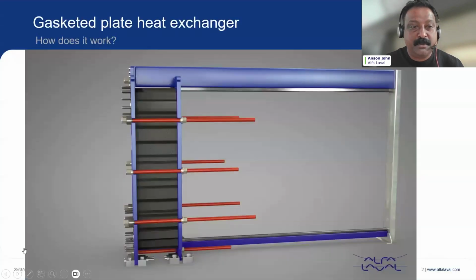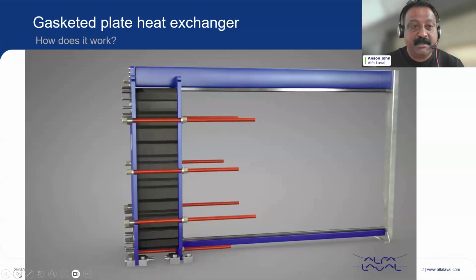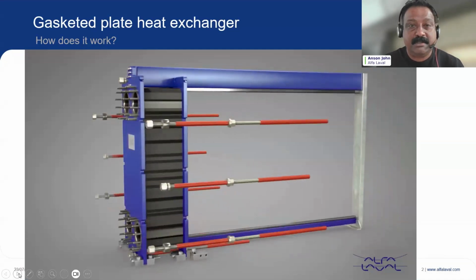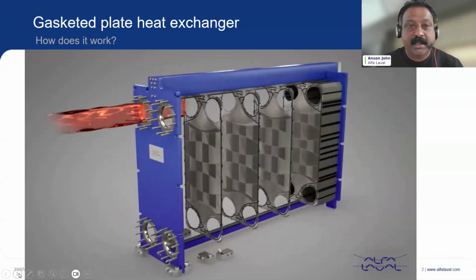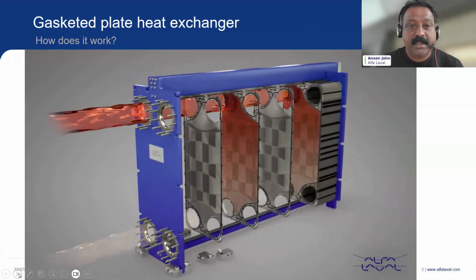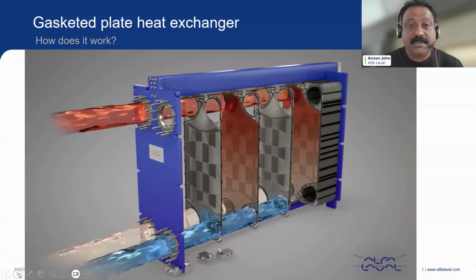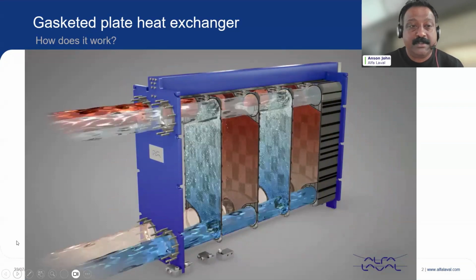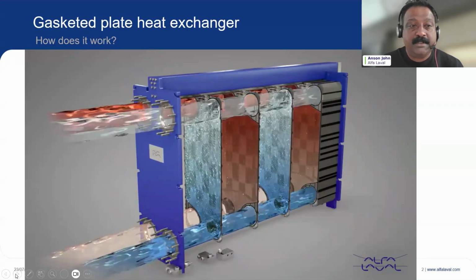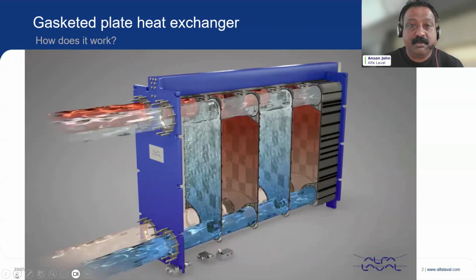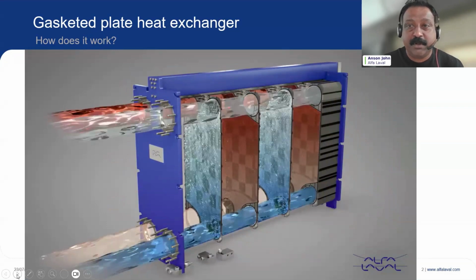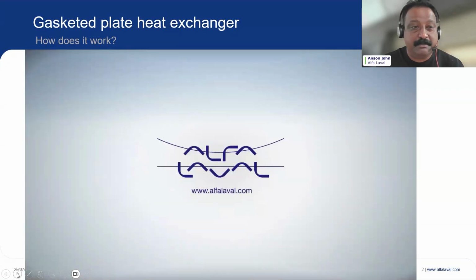So most of you know how a plate type heat exchanger works, but I would just like to show you the working principle of this heat exchanger. So I've got nuts and bolts and plates, and the hot inlet and the cold inlet on the other side. It's always counterflow because that's best for the heat exchange. It's very efficient. So this is how it looks, pretty simple, but there's a lot of R&D and engineering that has gone behind this.